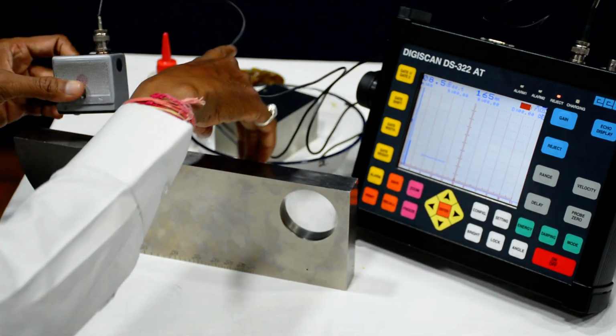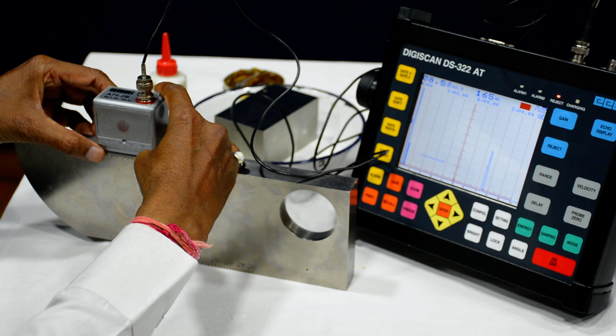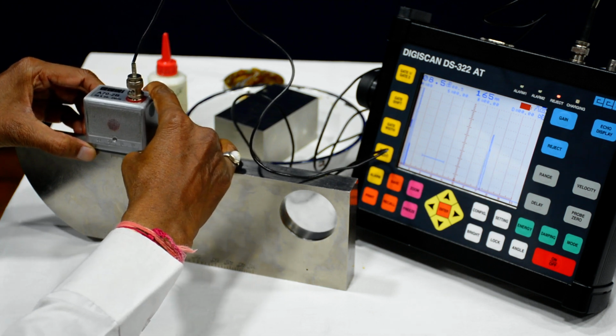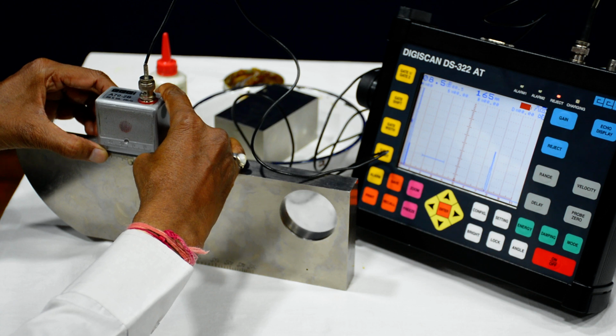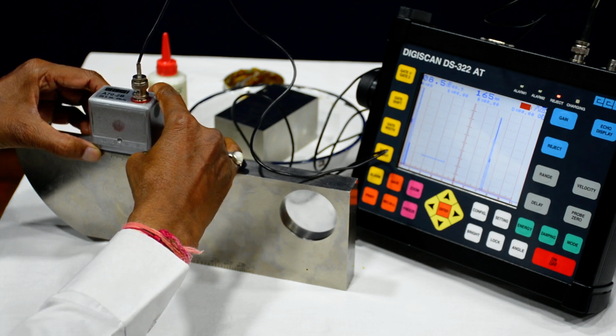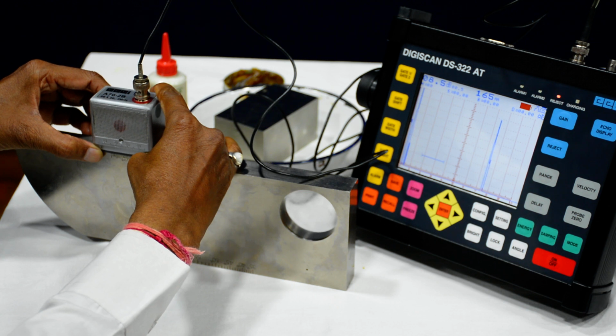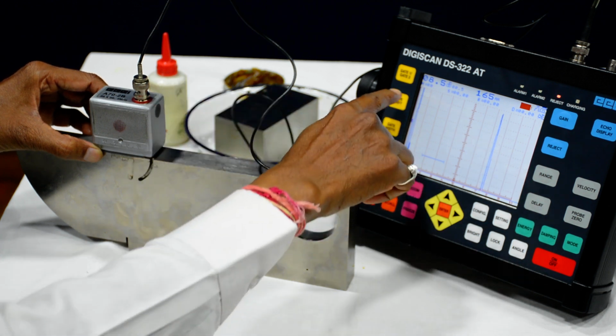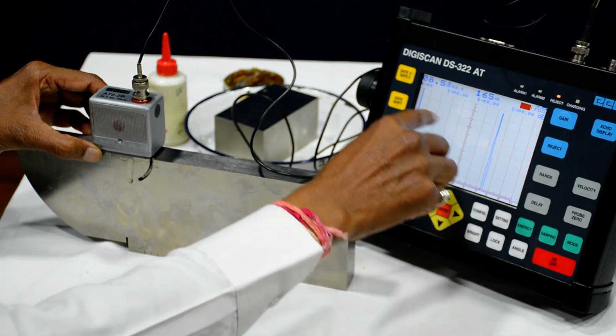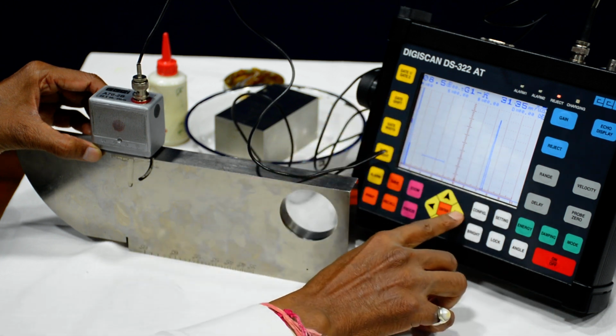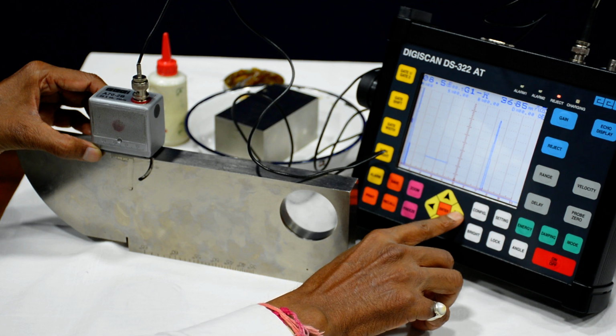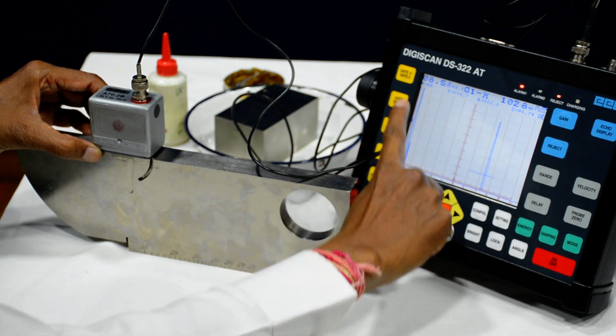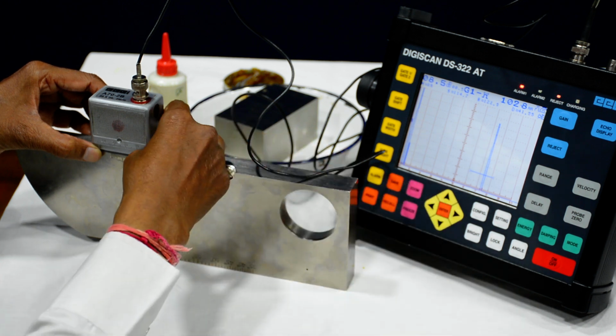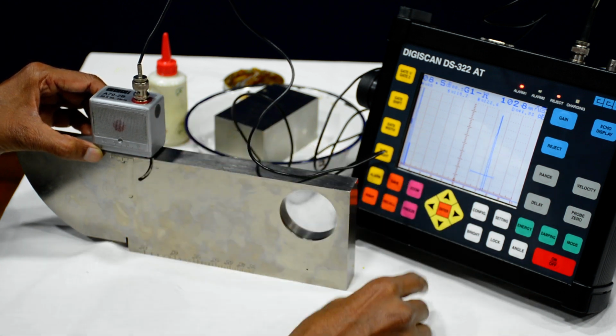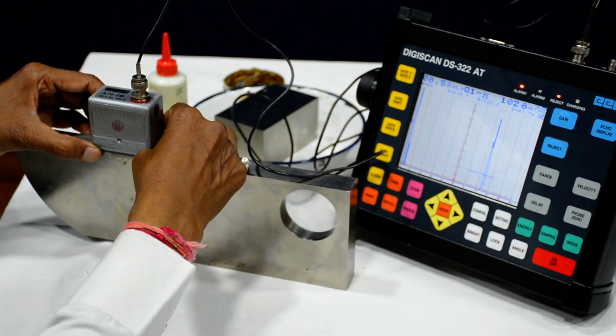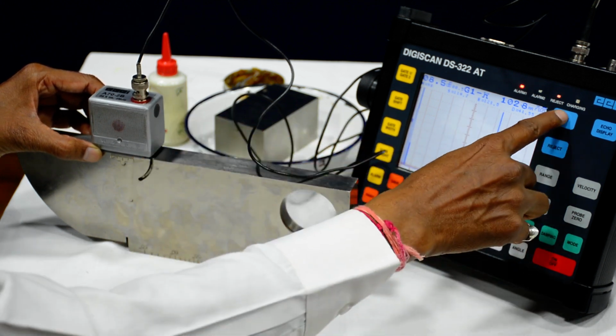Now we will place this probe at this location and we will move forward and backward. When the echo is appearing, whenever the height of this echo is maximum, that time we have to stop this movement. So for better accuracy, we can shift this gate at this. We have to touch the gate to that echo. So we will get the location where the height of this echo is maximum. It is touching the 100%, means first we will decrease the gain.